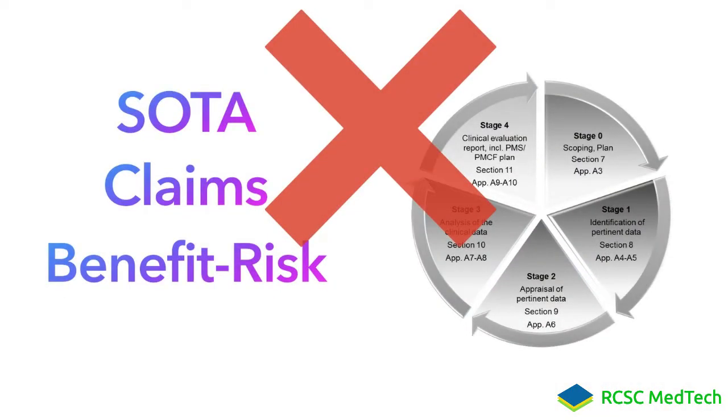Manufacturers do not need to consider CDP and CEP, state-of-the-art, particular claims, benefits, or even residual risks, because there is no strong connection between clinical evaluation and risk management. And it is not allowed to demonstrate equivalence if the manufacturer cannot legally obtain the technical, biological, and clinical characteristics of the other comparable devices. This is also why state-of-the-art is not applicable for the China CER. In summary, for the NMPA application, if you want to use the CER, the equivalence approach is the only way. If you cannot meet the prerequisites, you have to submit clinical investigation files.